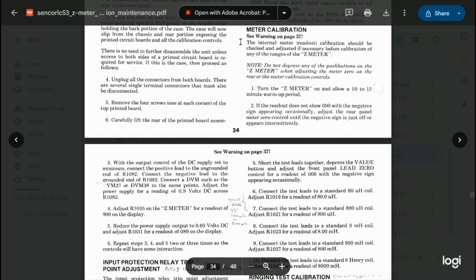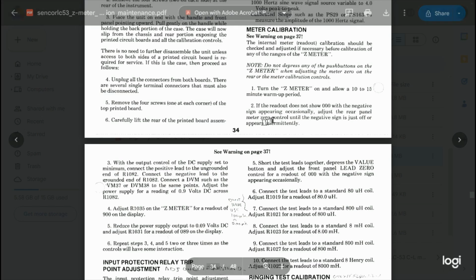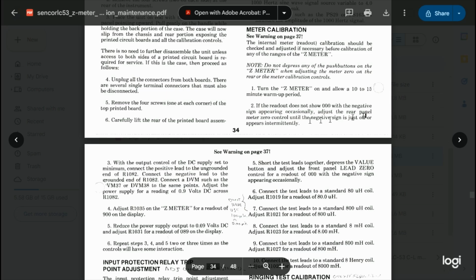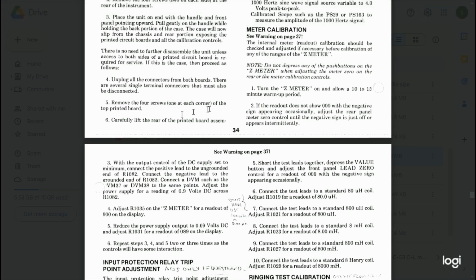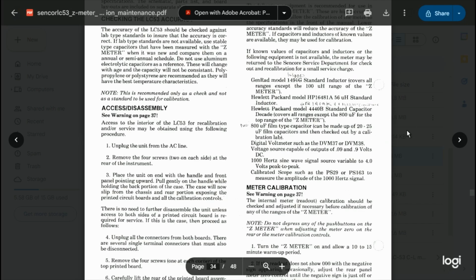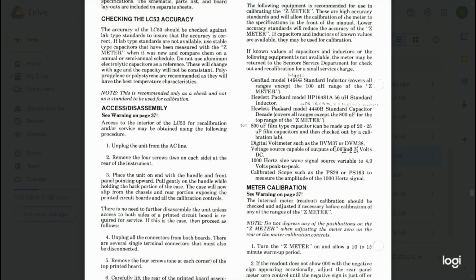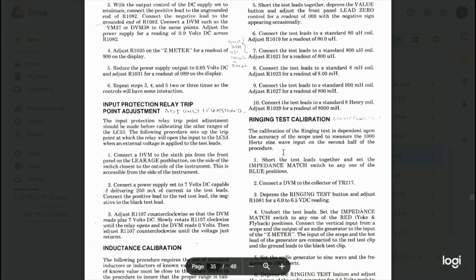It acts like a DVM basically, and there's a section where you go through meter calibration in the instructions. It says the internal meter readout calibration should be checked and adjusted if necessary before calibration of any of the ranges on the Z-Meter. So it says turn it on. If the readout does not show 000 with negative sign appearing occasionally, adjust the rear panel meter. This isn't the rear panel one, so we don't have to worry about it. Now, before this, they tell you that you're going to need a voltage source that is capable of putting out 0.09 and 0.9 volts, which is to be used in the calibration here.